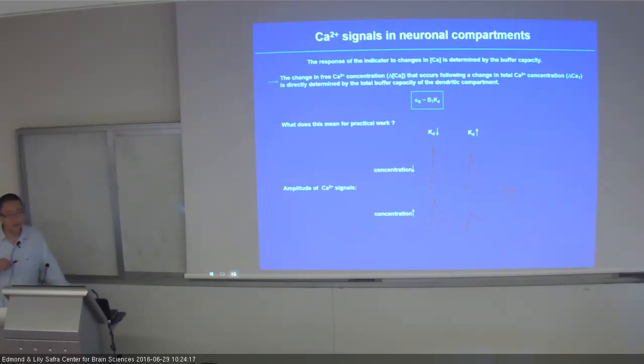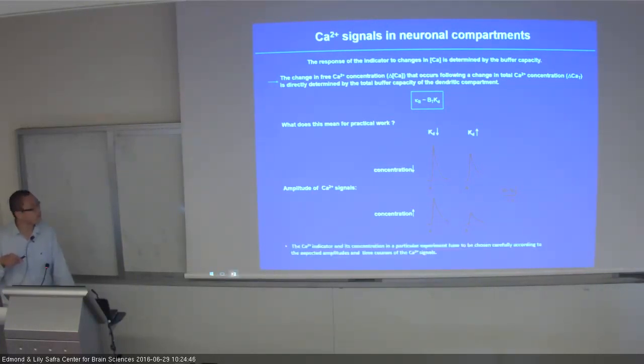And that's just for you to keep in mind when doing the experiment: how much dye you put into the cell matters for how much signal you get. And it's not always that the more dye you put, the more you get. You need to put in a certain amount in order to be physically sensible or detectable by the instrument. All instruments have a sensitivity threshold, but on top of that, it's not always so, it's the contrary. The more you put, the less sensitive it is.